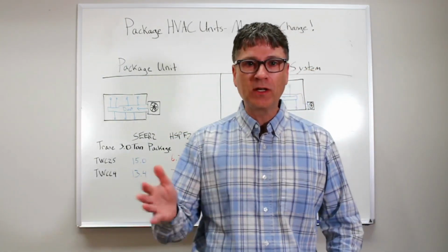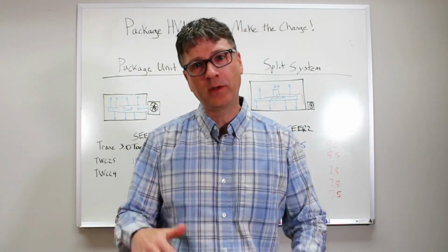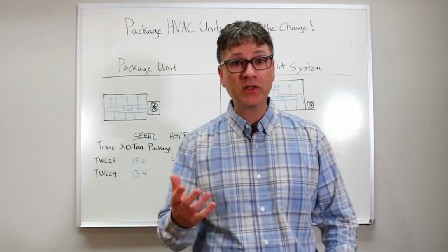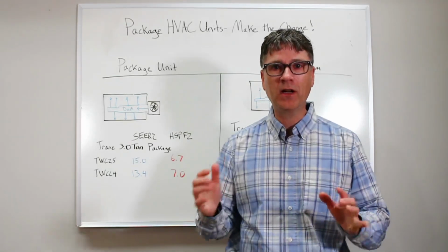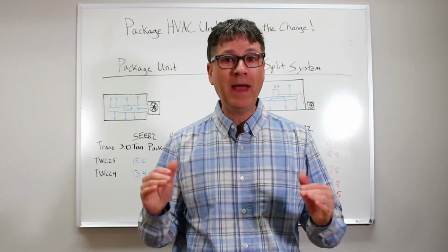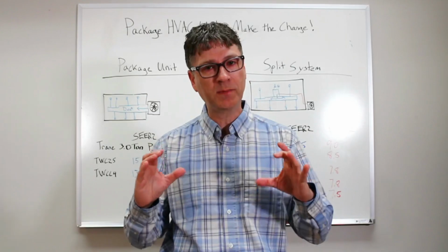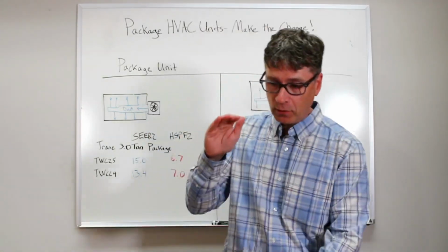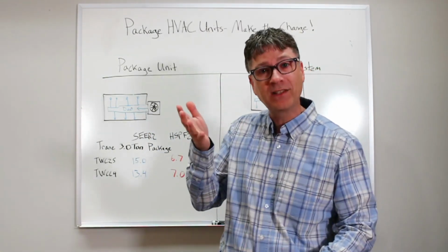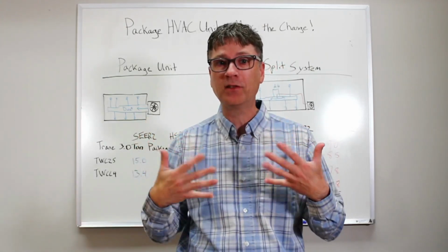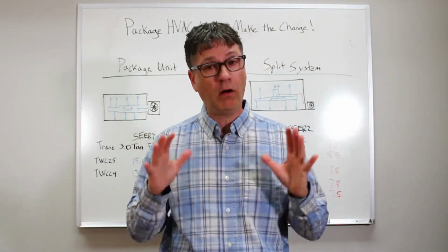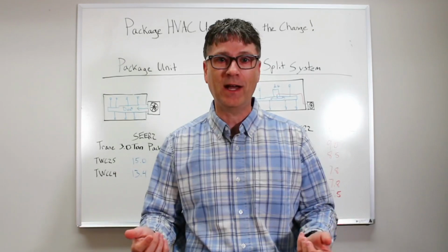So let's look at some of the good points of package units before we get into some of the problems. First off, because the entire system is outside, a package unit can work in a crawl space that's really short. If you only have enough room for ductwork, that's okay, because everything else—the air handler, the condensing unit, all the equipment—sits outside.